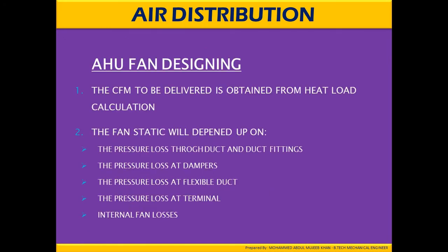AHU fan designing: the CFM to be delivered is obtained from the heat load calculation. The fan static pressure depends upon the pressure loss through the duct and duct fittings, the pressure loss at the damper, the pressure loss at the flexible duct, the pressure loss at terminals, and internal fan losses.